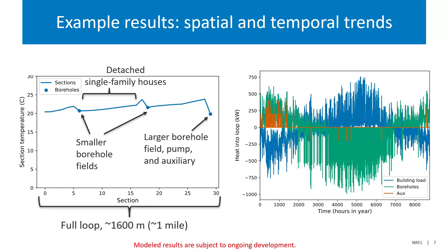As a quick example of outputs: on the left we're showing spatial trends — as you move around the loop, you see temperature changes, consistent with what was mentioned earlier. On the right, every hour throughout a year showing how heat is being exchanged with the loop: building loads and borehole loads in blue and green are generally opposite. In winter, buildings take heat out of the loop and the borehole field puts heat in; we see the opposite in summer. You can identify where auxiliary heat might be needed and consider trade-offs like an electric boiler versus drilling more boreholes.